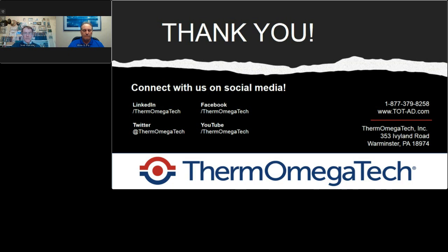Right, certainly. Now, you did mention that the response time is longer for thermostatic valves compared to electronically controlled. Can you put any sort of numbers on that? Yes, definitely. For the solenoid valves, we were saying they react within milliseconds. For the thermostatic actuators that we use, typically around 15 seconds, depending on what the delta T is. If you're going from 100 degrees F and you hit it with a step response of 200 degrees F, the actuator will stroke all the way out probably within 7 or 8 seconds, maybe 10. But if you're only going from 100 degrees to 110, it might take a little bit longer because your thermal pressure, so to speak, isn't as great.